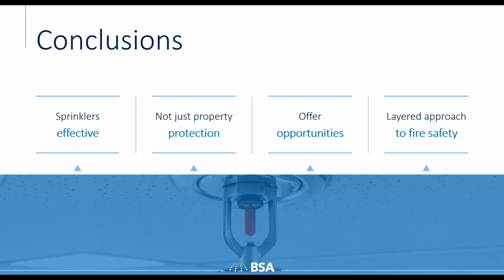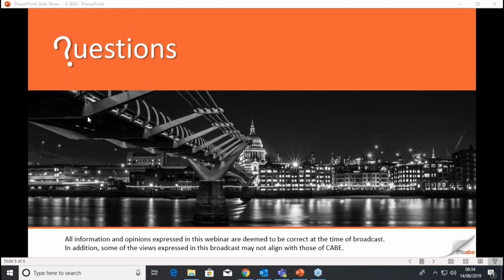Yes, in terms of accidental activations or sprinkler heads failing, it's a very rare occurrence. When sprinklers do misoperate, there's normally another factor involved. For example, we've seen sprinkler heads affected by cold weather so that they freeze, and nobody knows they've frozen until they subsequently leak.